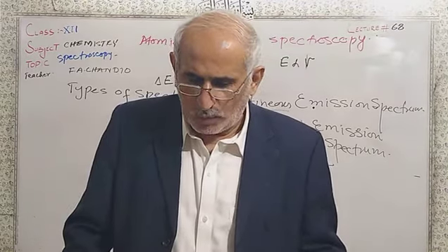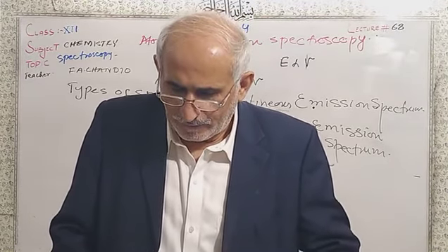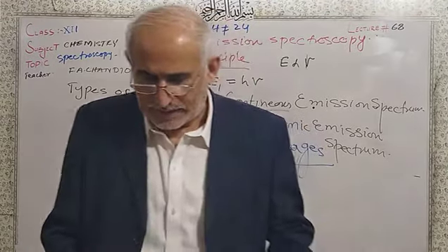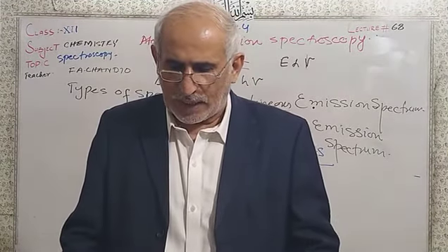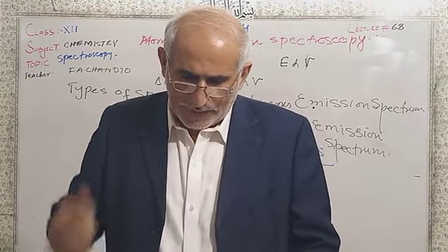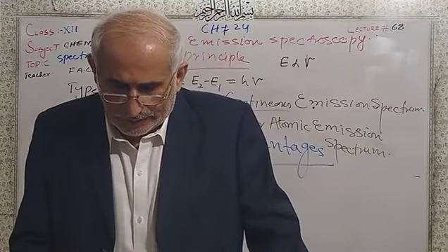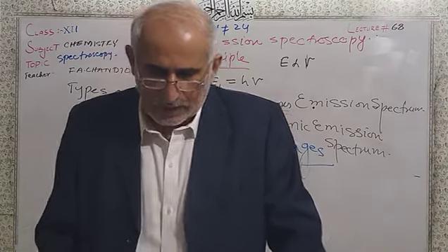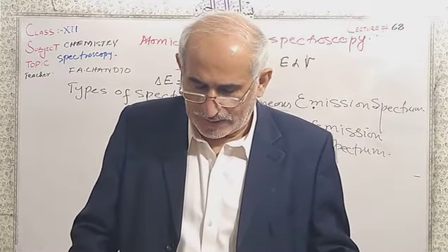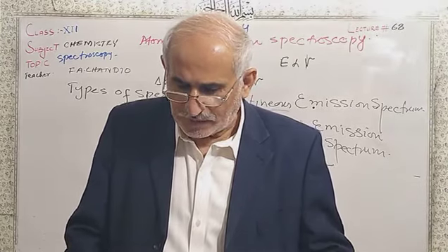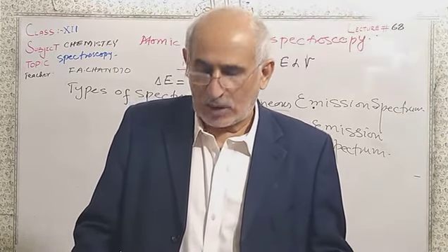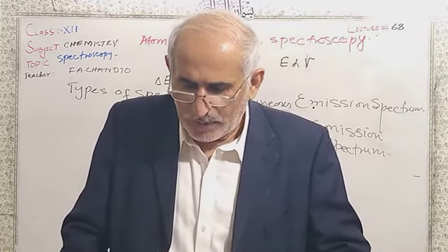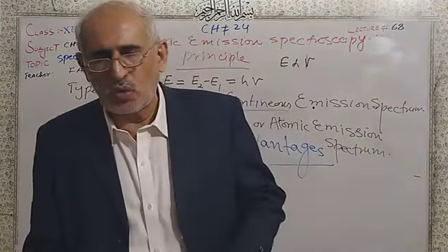This analysis can be performed either in the solid or liquid state with almost equal convenience. This technique requires minimum sample preparation, as a sample can be directly introduced into the spark, solid or liquid. The technique provides results very rapidly. If automated, time required is just 30 seconds to 1 minute. This method has been used for a wide variety of samples like metals, alloys, paints, geological specimens, environmental and biological samples can be analyzed by using this technique.